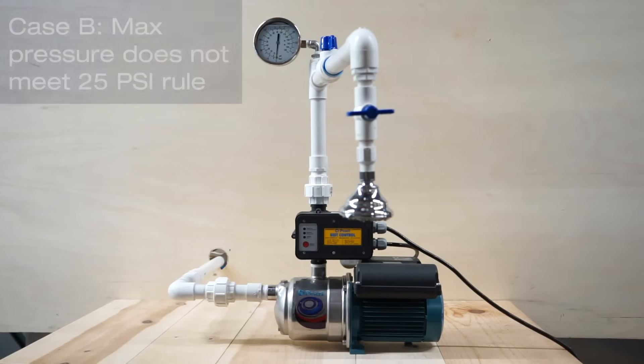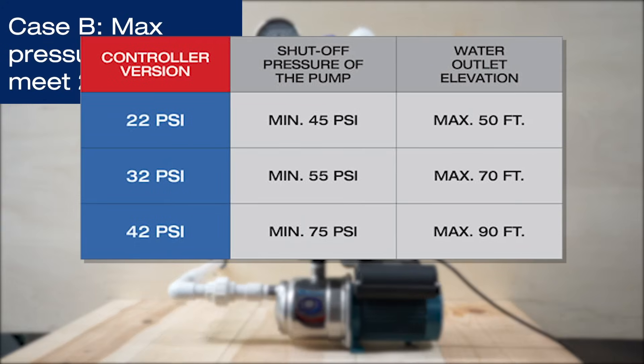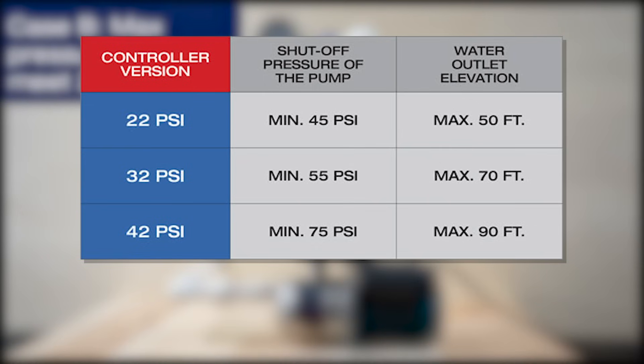In case B, when installing a best control controller on a pump, keep in mind the following. The difference between the shut-off pressure of the pump and the starting controller PSI setting must be at least 25 psi. This is known as the 25 psi rule.